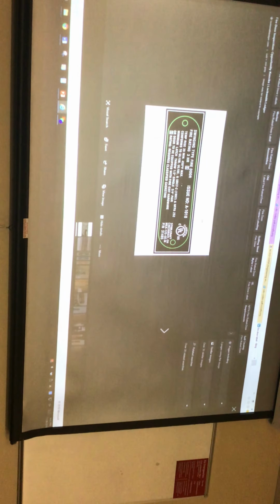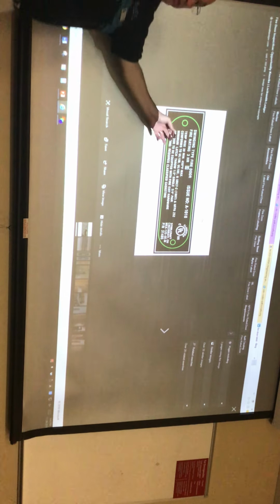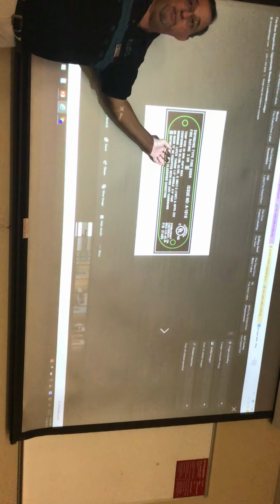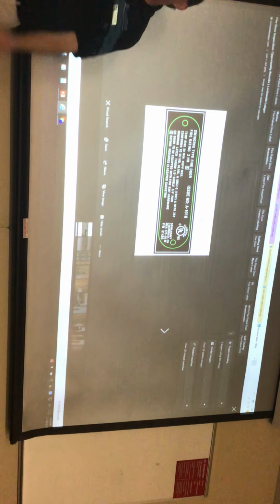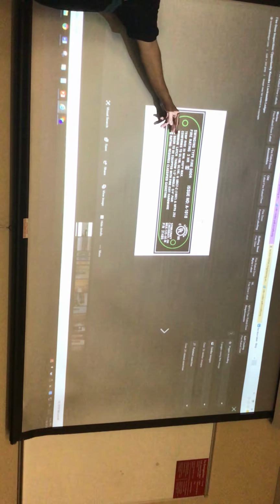Now, this is what you're talking about, these kind of signs here, JD, but that's not really what we're looking at. We're looking at these labels. So when we've got a door that's labeled, or that's a fire door, it could look just exactly like that door and have no difference to it whatsoever, other than the label on the end of it. So on the top of it or on the back of the leaf, it's going to have this label, say that UL certified, this one's a 3-hour door. The S means it's also smoke label. So this one can go in a smoke barrier because it's both fire and smoke resistant. And it tells you what standards it conforms to. And this temperature rise they're talking about is on the opposite side of the door, how hot the opposite side's going to get. Did I show you the 3-hour door video?